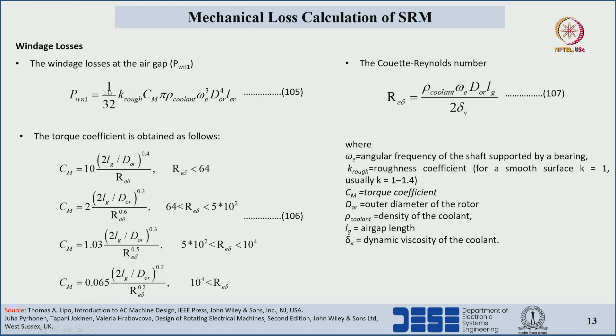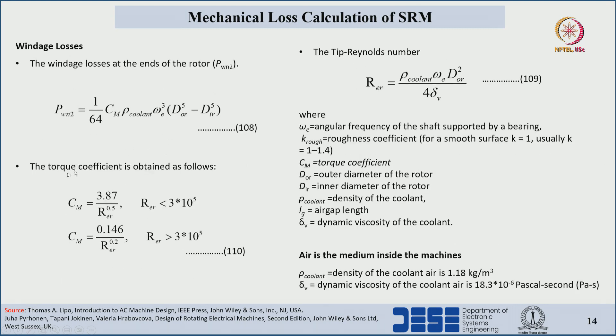The windage loss equations show how Reynolds number influences windage losses. Different Reynolds numbers yield different windage loss values. Torque coefficients for windage losses at the ends of the rotor are also defined, using the tip Reynolds number in the calculation.